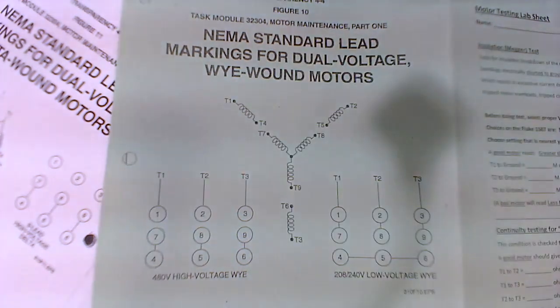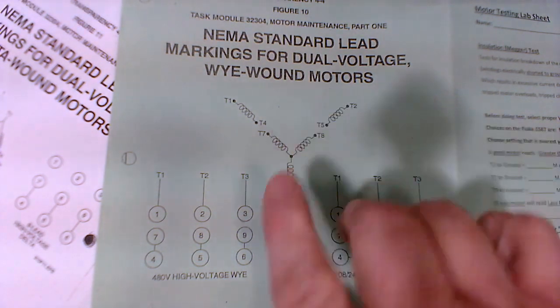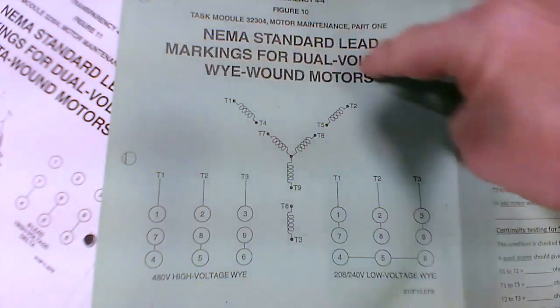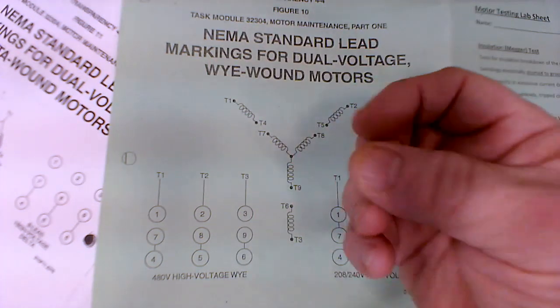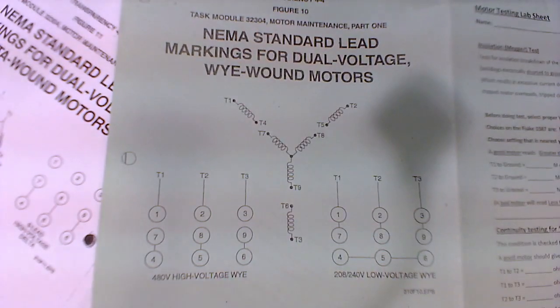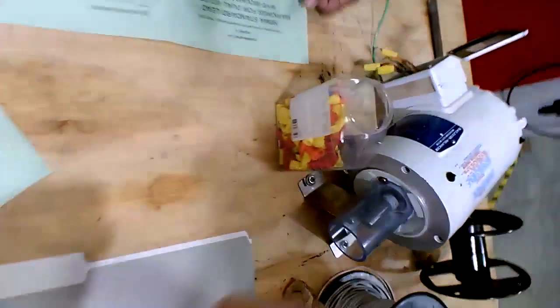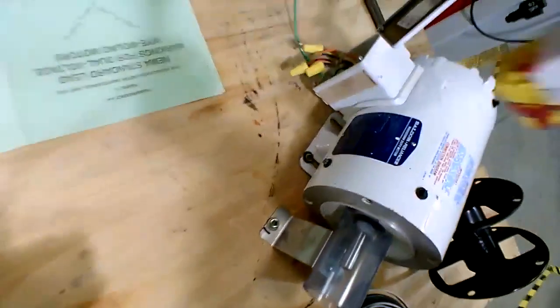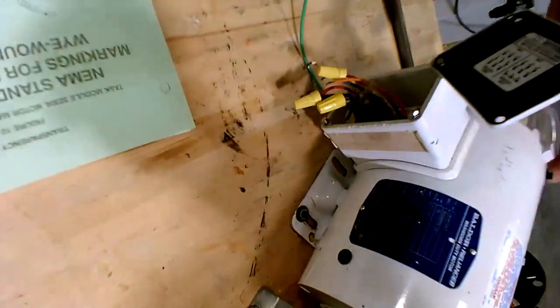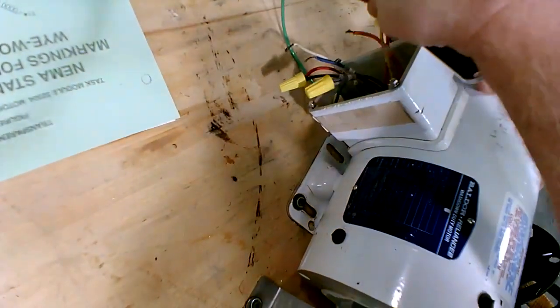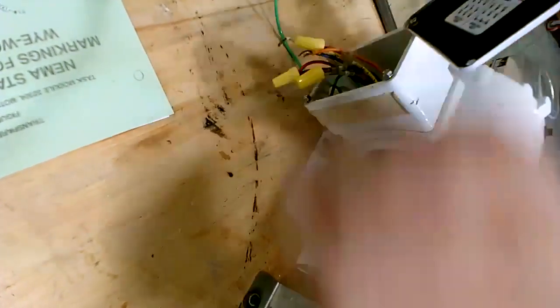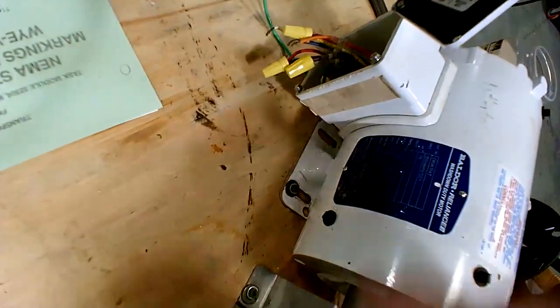These are the internal windings in that motor, and that's how they look inside. That's the way it's actually made. It's in a Y configuration. And you have 9 wires, T1 through T9, that are loose whenever you go to the cat head or the enclosure. As you see there, you have those 9 wires there. Some of them have already been paired up.